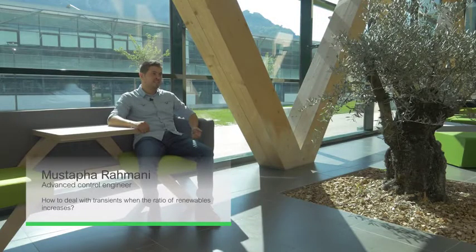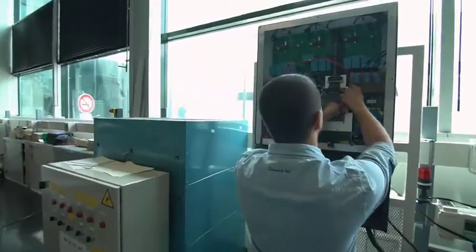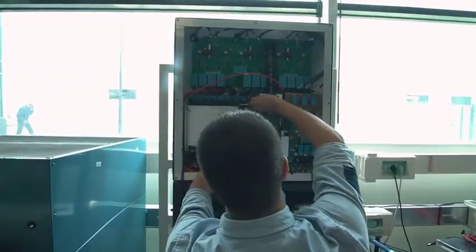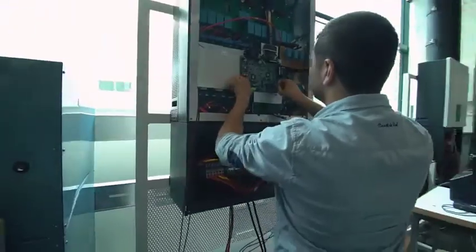One of our objectives today is to increase the proportion of renewable power generation in microgrids. This means replacing the traditional rotating machines of the gensets by renewable power sources interfaced to the microgrid by means of inverters. However, if traditional grid-tie inverters are used for this purpose, the microgrid can become highly unstable for many reasons: the lack of inertia that was initially provided by the rotating machines we want to replace, the fact that traditional grid-tie inverters are not grid-forming, and obviously the fact that the PV or wind power sources are intermittent.